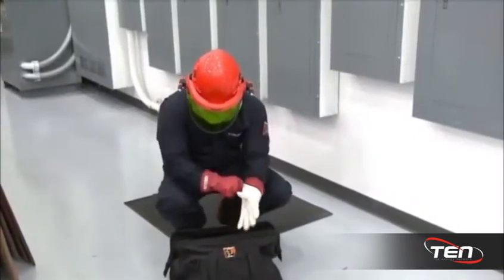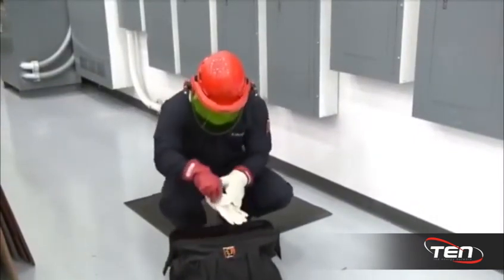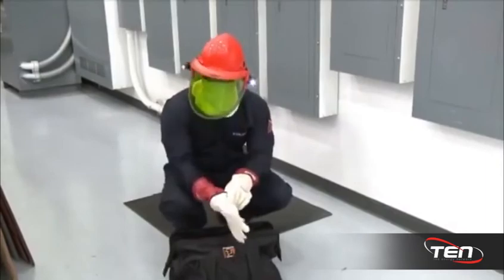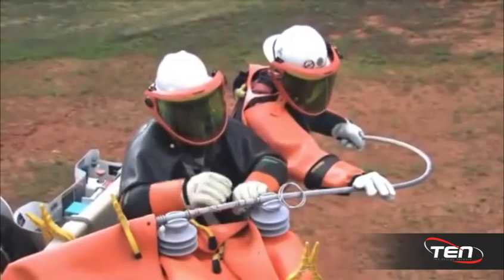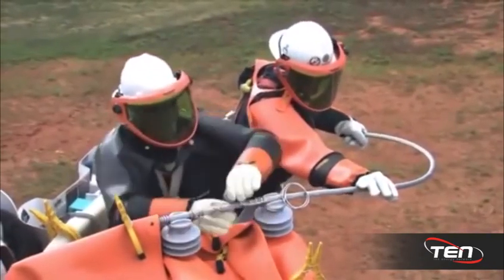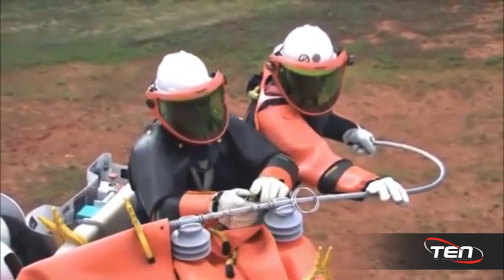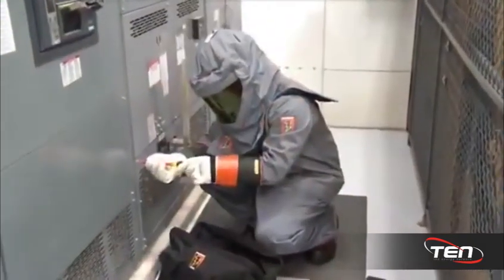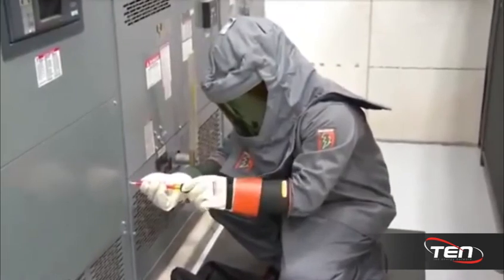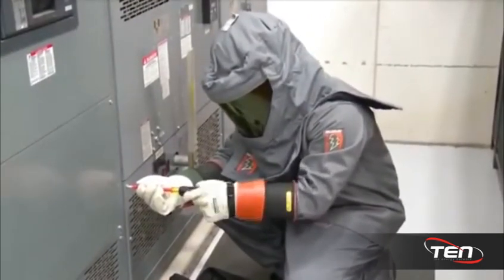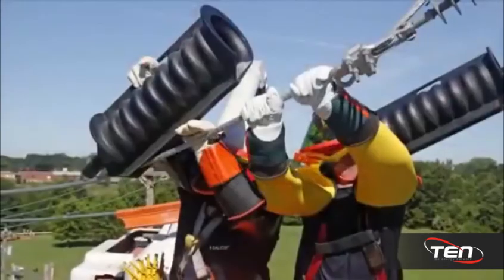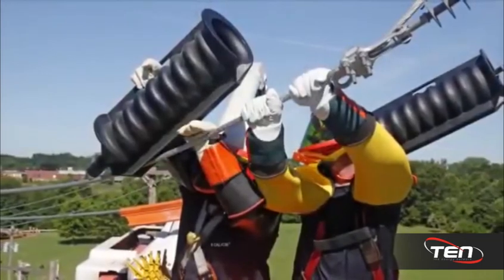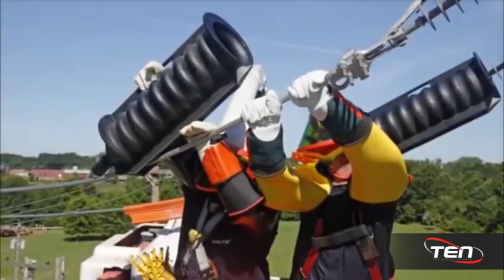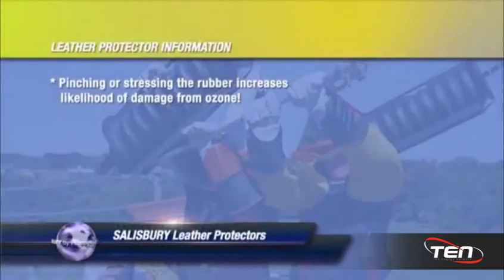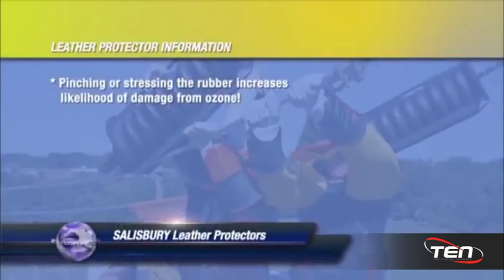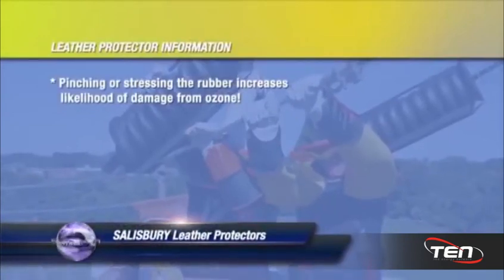An important accessory for insulating rubber gloves are leather protectors. Leather protectors should always be worn over electrical insulating gloves to provide needed mechanical protection against abrasions, cuts, and punctures. Leather protectors should never be used as work gloves, and work gloves should never be used as leather protectors. Leather protectors are specially designed to fit over rubber gloves without pinching or stressing the rubber. By pinching or stressing the rubber, there is an increase in the likelihood of damage to the gloves from ozone.